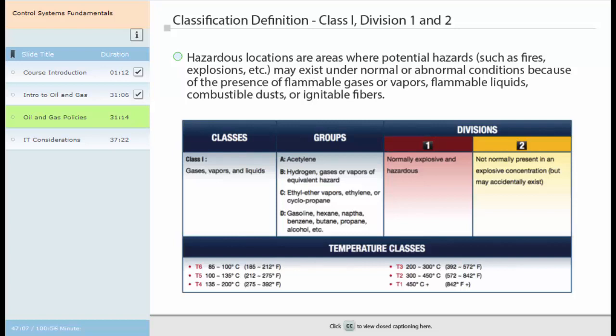According to NFPA's National Electric Code, there are three types of dangerous locations. Class 1 includes vapors, gases and liquid. Class 2 includes dust. Class 3 includes flying debris and fibers. The division assigned to a location determines how frequent hazards occur. For example, Division 1 means the location is typically explosive and hazardous, while Division 2 means the hazard is not normally present but may accidentally occur.